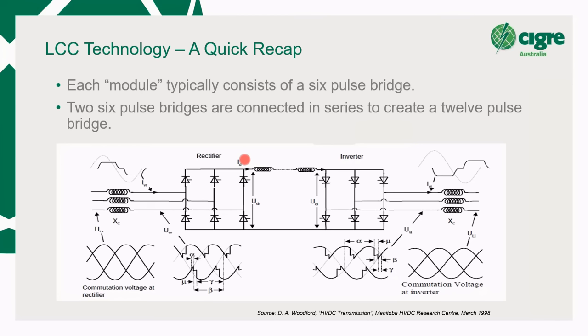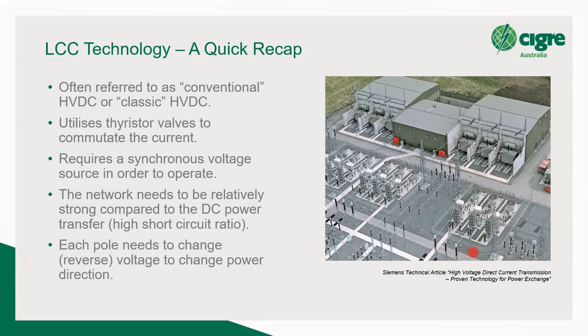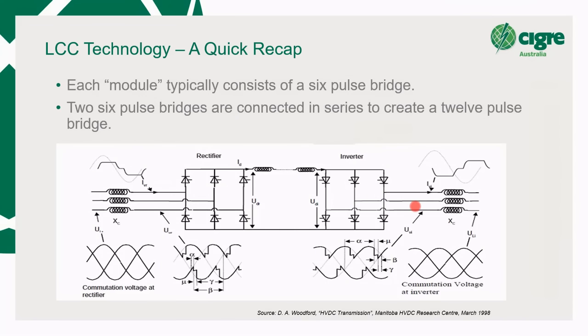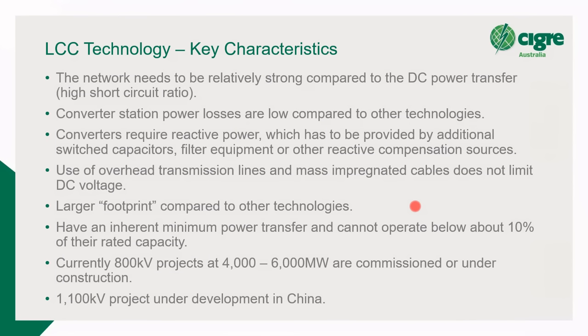So what that leads to, if we take this example from Siemens, is the converter hall and transformers being relatively small, but quite a large footprint being needed to put in all the filters for those purposes. So key characteristics: need a relatively strong network. Converter power station losses tend to be lower in LCC. VSC technology is catching up, but still not quite there. There's still a fair amount of heat loss in the VSCs. Converters require reactive power, so they require filters.